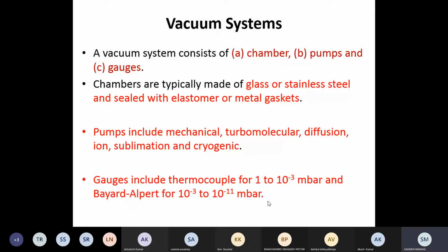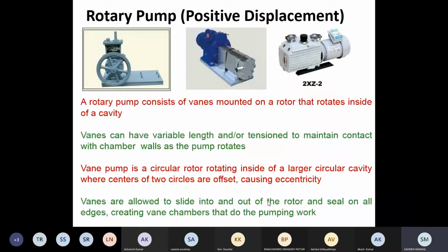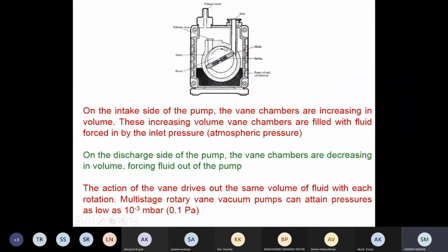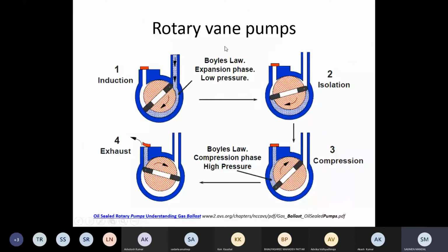So this is a rotary displacement pump, and this is how it looks. Inside, the motor is there, and it will rotate. I have a schematic diagram, so we can understand how it works. So, the rotary vane pump, how it works. First, you can see the piston movement. In this situation, the shaft will move. It is a rotating shaft, and you can see how it's moving.